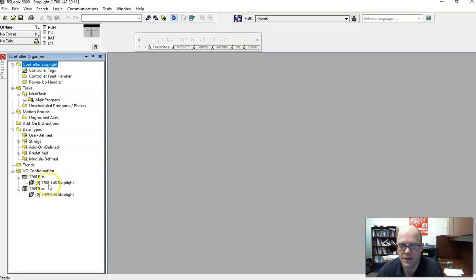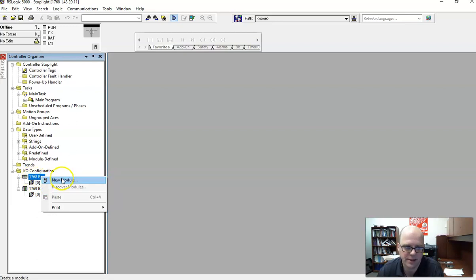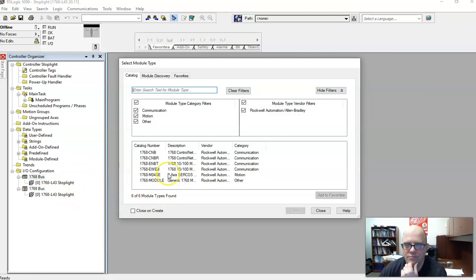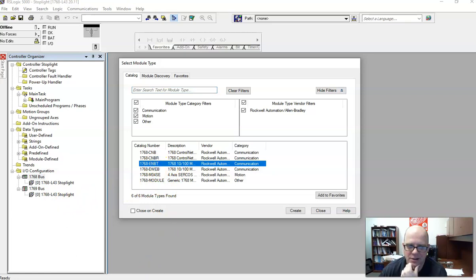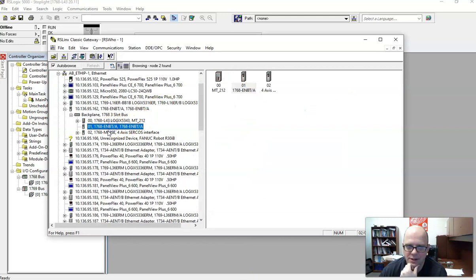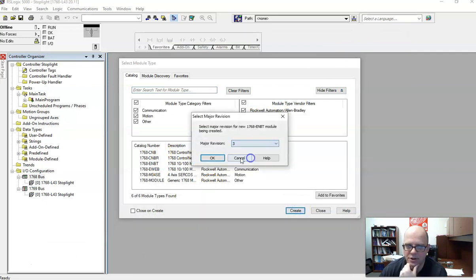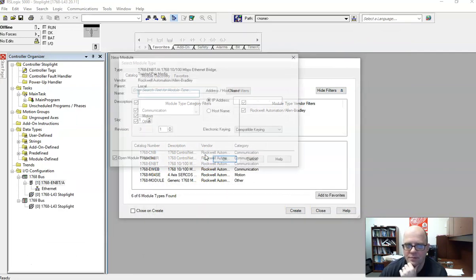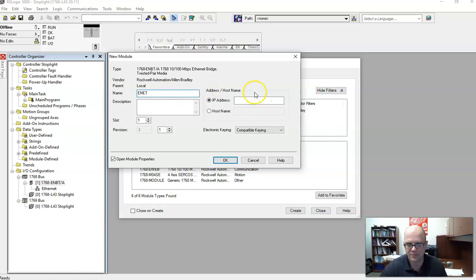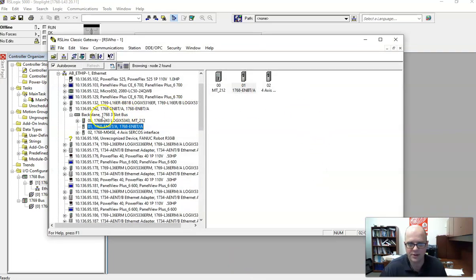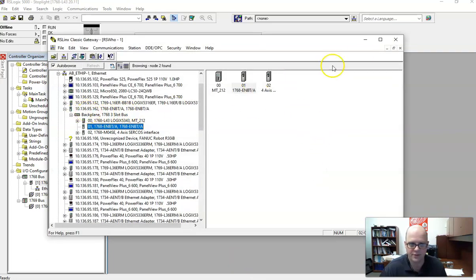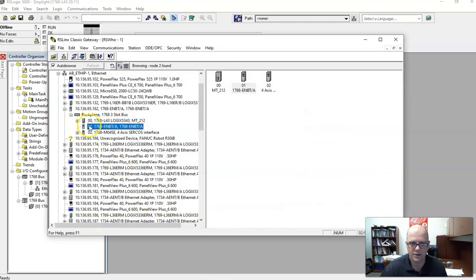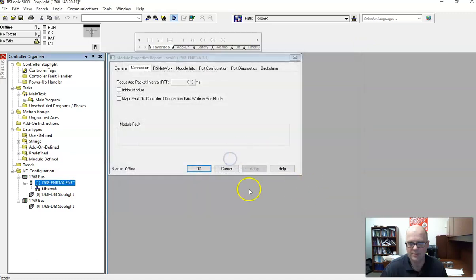Notice down here there are two things that we will need to add. First things first, right-click on the 1768 bus, hit new module, and we need to add the communication card. So let's add the communication card. It's this one right here, but if you want to double-check on RSLinx, you can see it's ENBTA. So I'll hit Create, Make sure Revision 3, hit OK. And we can just call this ENET for the card and put in the IP address. And how you get the IP address is right here from RSLinx. So in my case, it's 10.136.95.162. It's going to be in slot 1, and if you don't know, look at this little number right here. This is the slot it's in. Hit OK. That way the hardware is there.